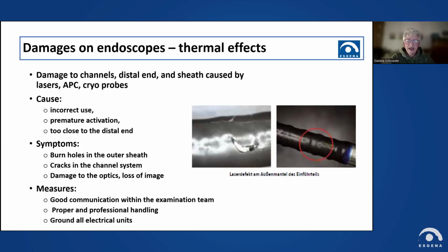Or you have accessories with physical properties like laser, APC, or cryoprobes. These are with higher temperature. This one really with a low temperature, which can then cause a kind of explosion in the channel if you don't move it or use it correctly. So premature activation, too close to the distal tip, for example, can burn holes or damage the channel due to the low temperature.